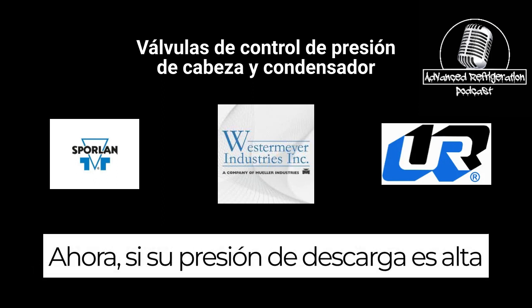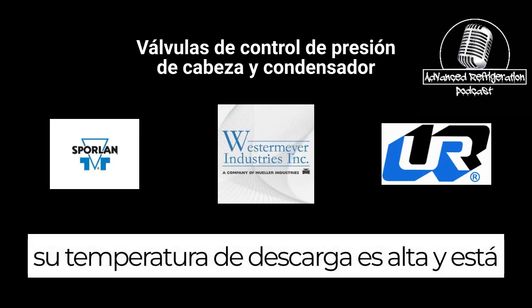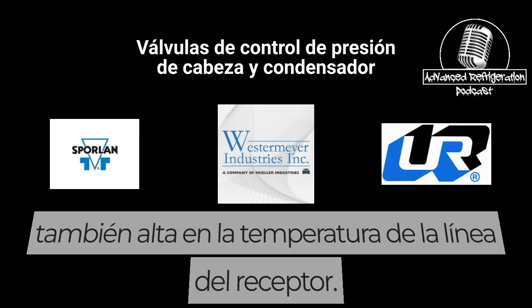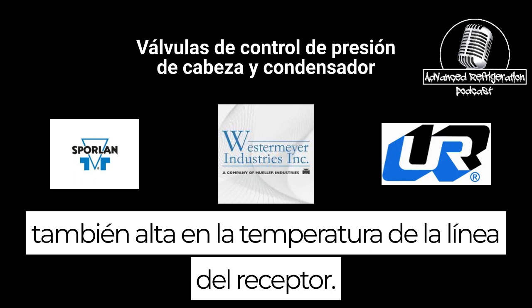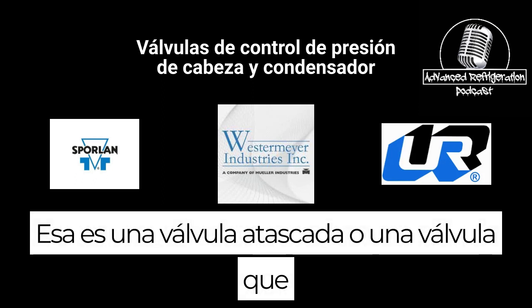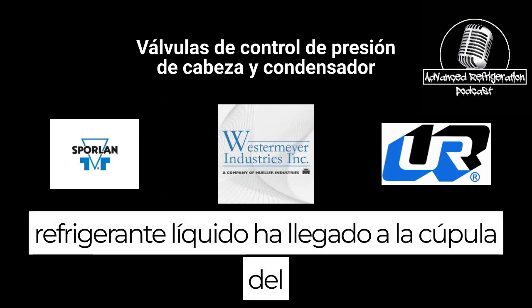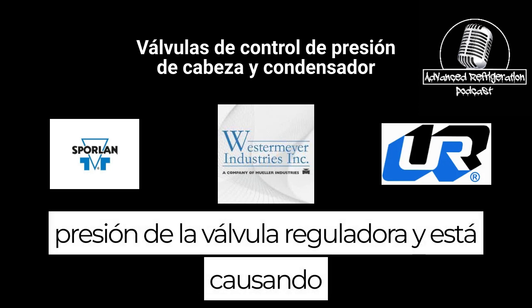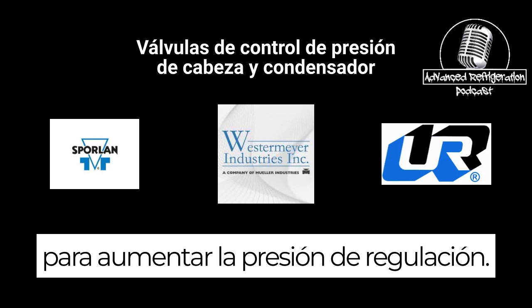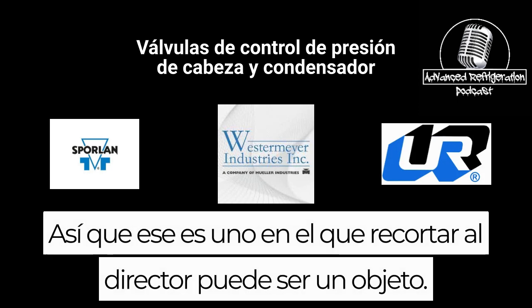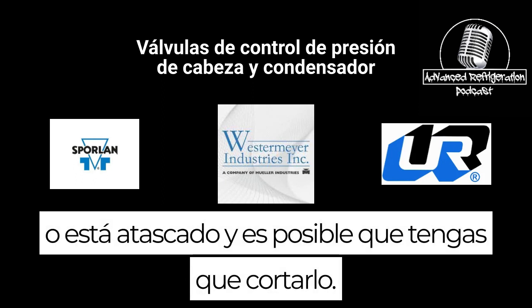Now, if your discharge pressure is high, your discharge temperature is high, and you're also high on your receiver line temperature, that is a stuck valve, or liquid refrigerant has gotten to the dome of the pressure regulating valve and is causing it to increase the regulating pressure.